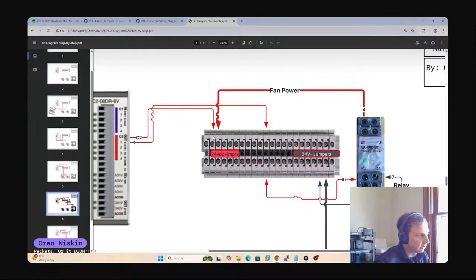A soft start is an electronic way to slowly ramp up that motor without it drawing so much current at first. It does that by holding back the electricity. A relay works by sending current through one part, which activates an electromechanical switch that then switches on another source of power. You'd send control power to the soft start to tell the motor to start, and that would cause your motor to start, but you'd also have a relay in line as part of that control mechanism. So it's very similar, in the same arena for sure.